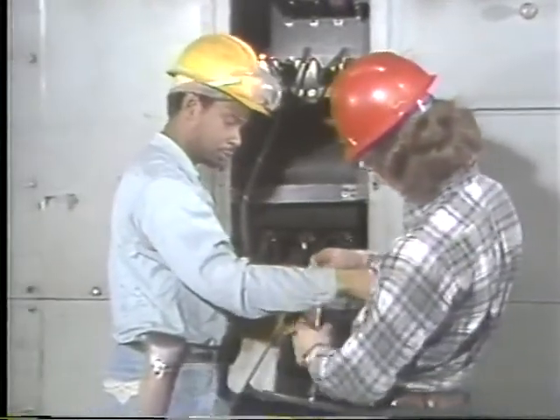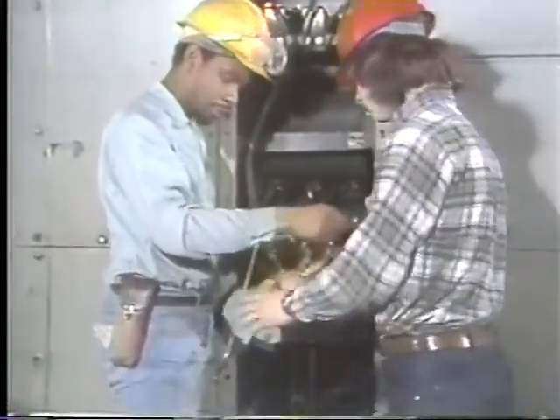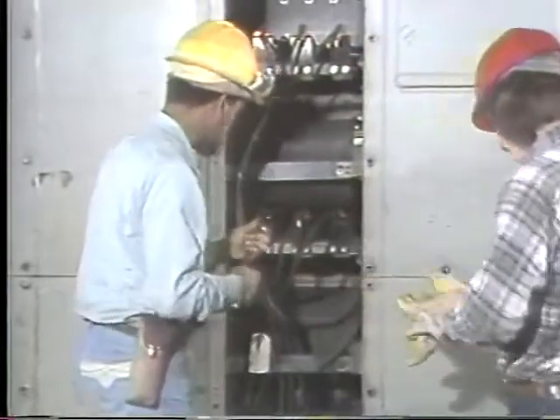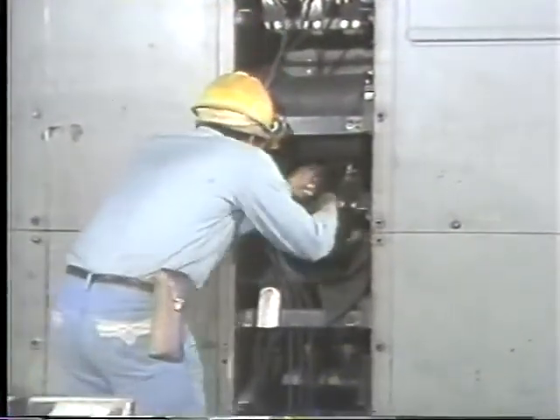The wrench is tied to his wrist with a lanyard before he reaches in. That way, if he drops it, it can't bounce off the rubber and short out bus bars below. Shorting the main bus would knock out a lot of equipment and make an arc that could burn or temporarily blind the electrician.